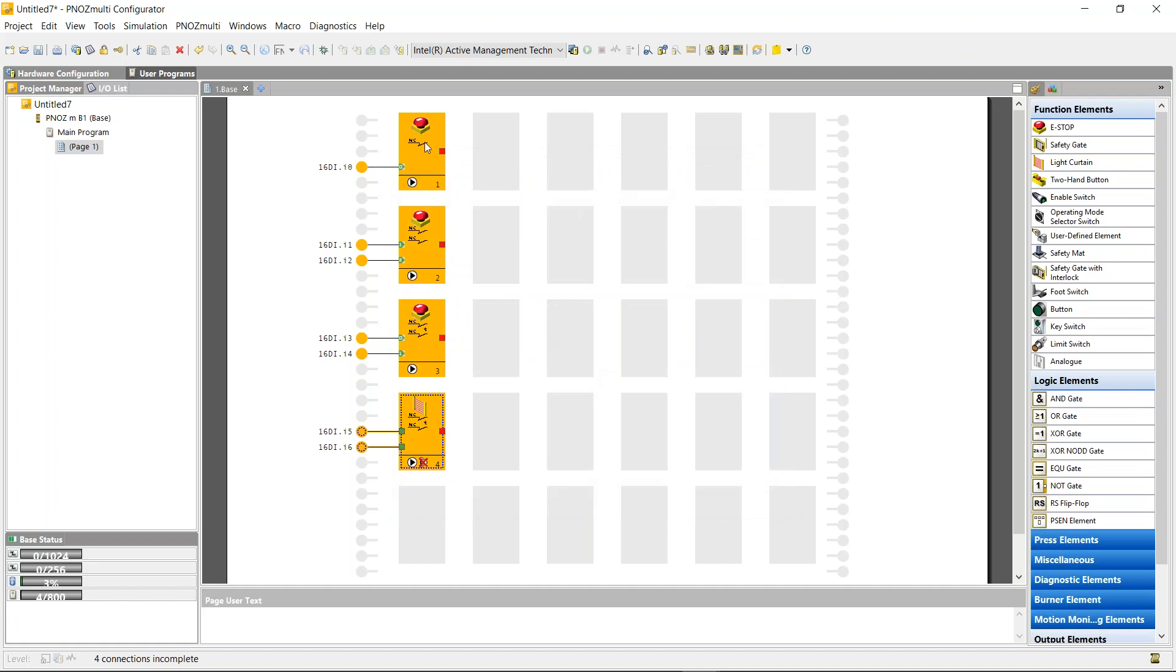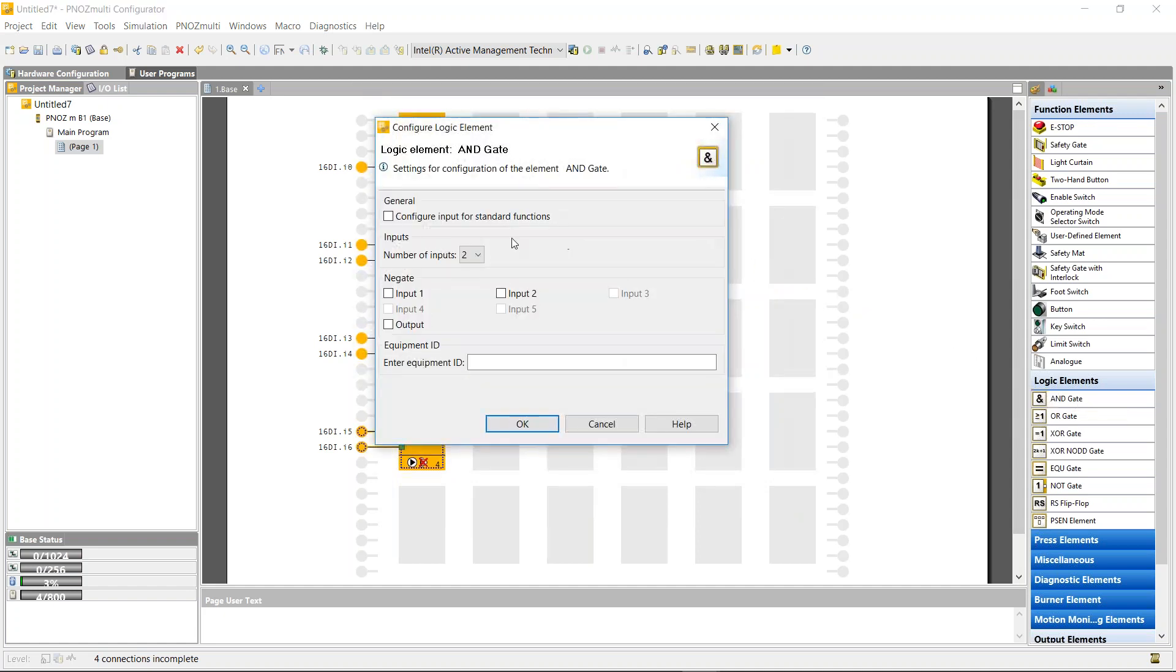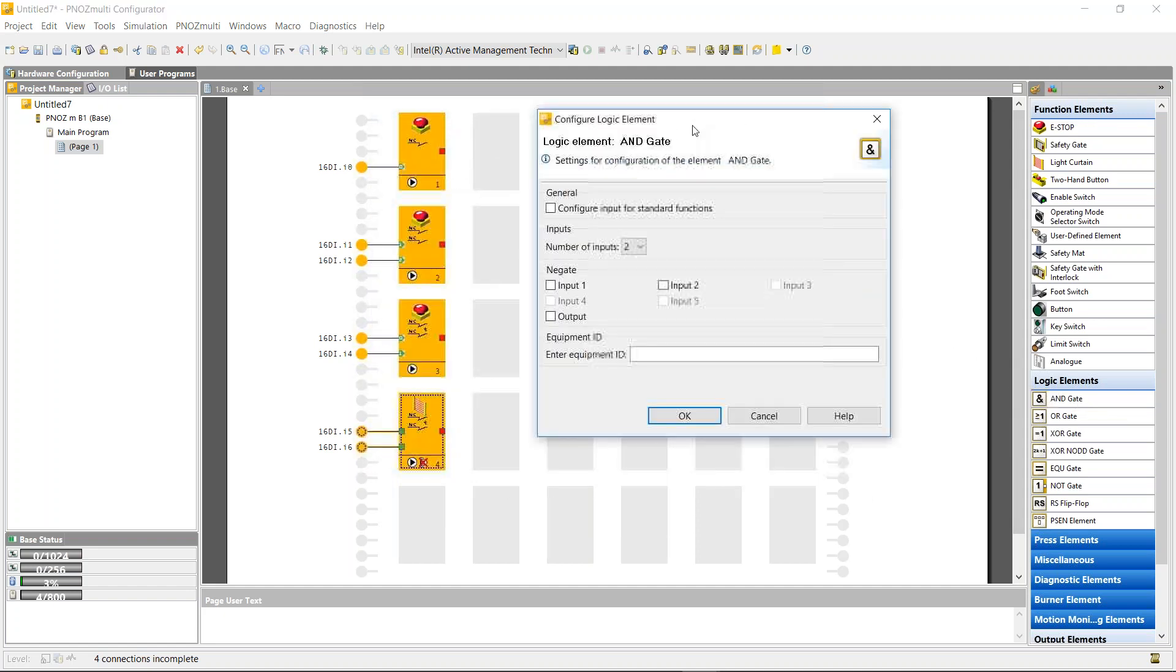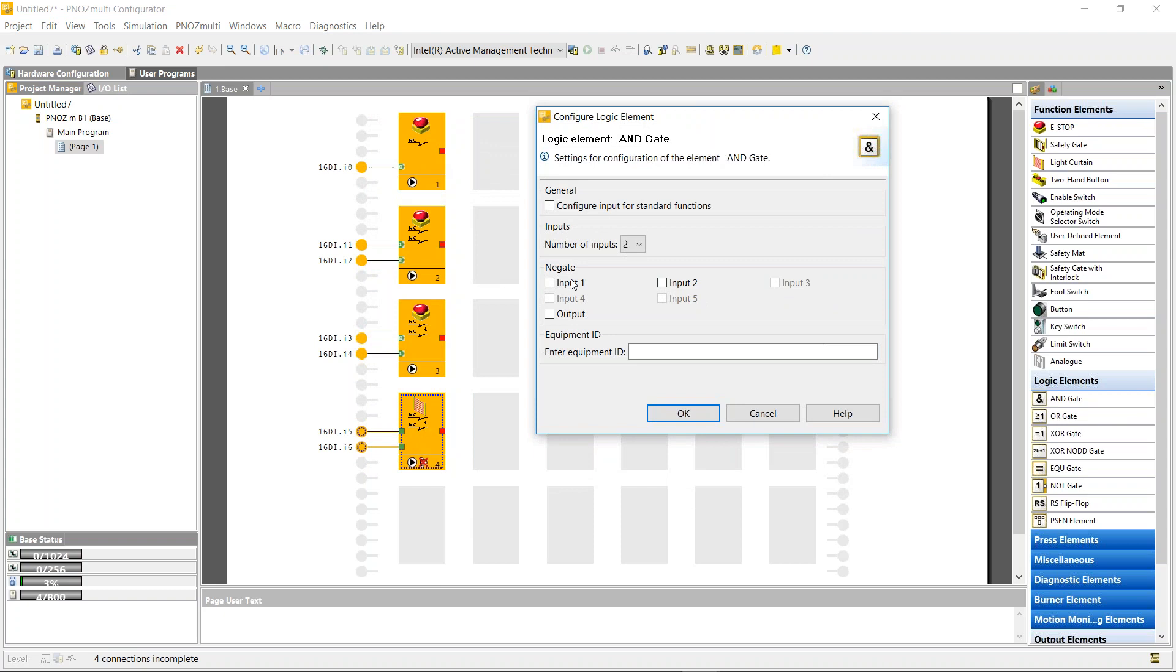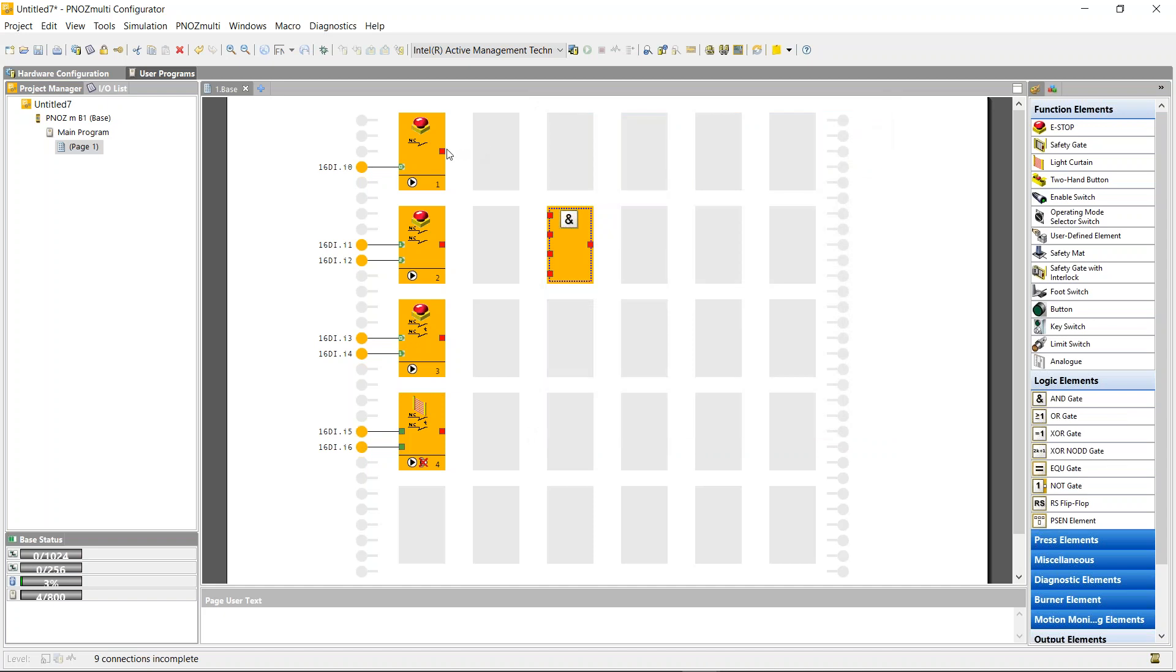In my safety matrix, I want all the inputs to shut off the same output. I'm just going to use a logic block, the AND gate. Since I've got four inputs, I have to change the AND gate to four inputs. Now I can just drag and drop to each one.